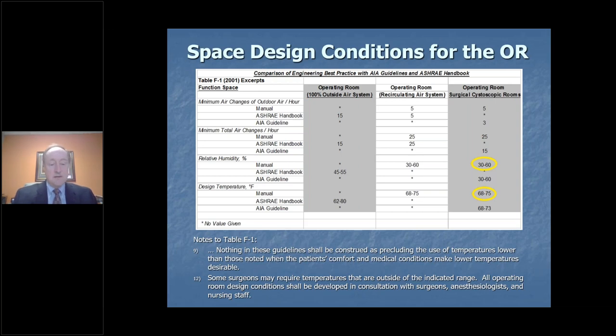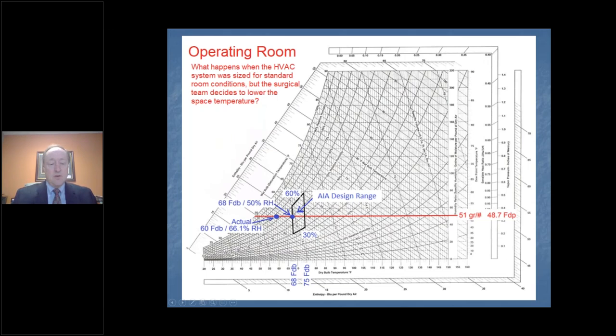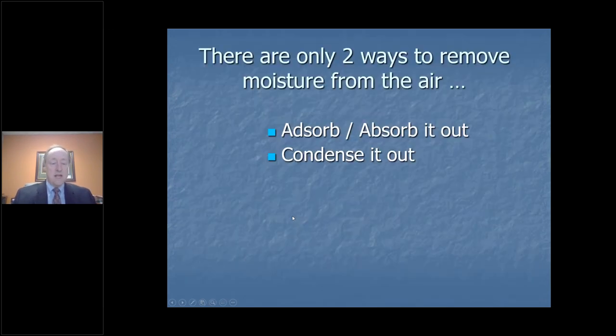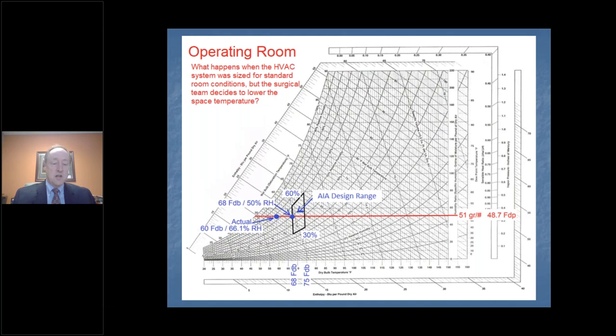So this is just a graphical illustration of that. Let's say you design for that 68 to 75 degree window and 30 to 60%, and you even designed on the low end of that, so maybe that is your point right there that you designed for. But now your surgeon comes in and tells his or her staff to drop the temperature as low as possible, and they drop it down to 60 degrees rather than 68. Now you'll see right here that the relative humidity is actually 66%.